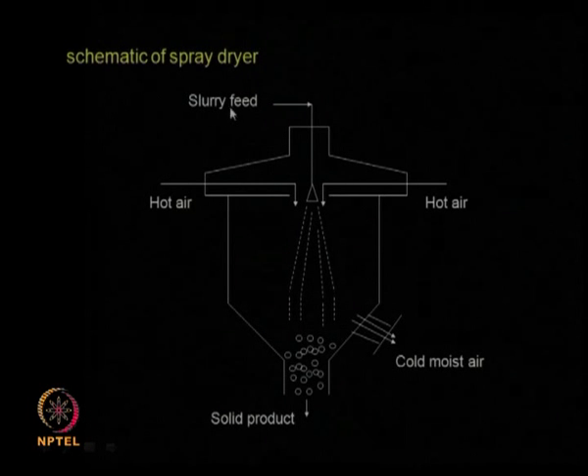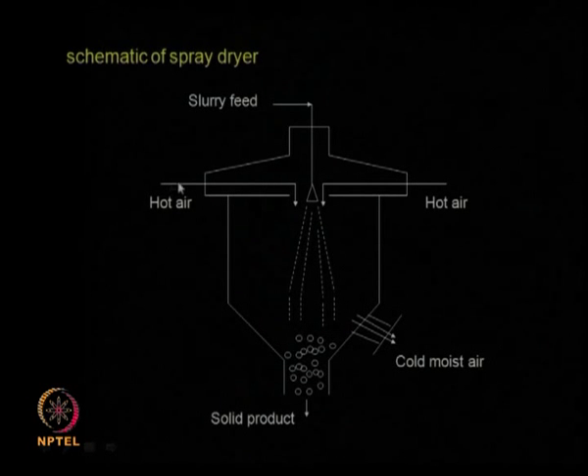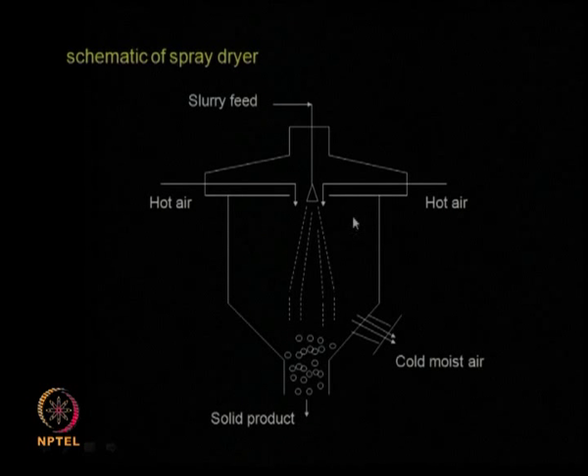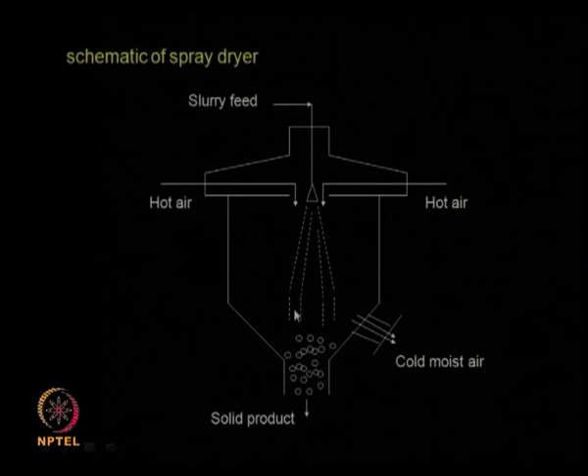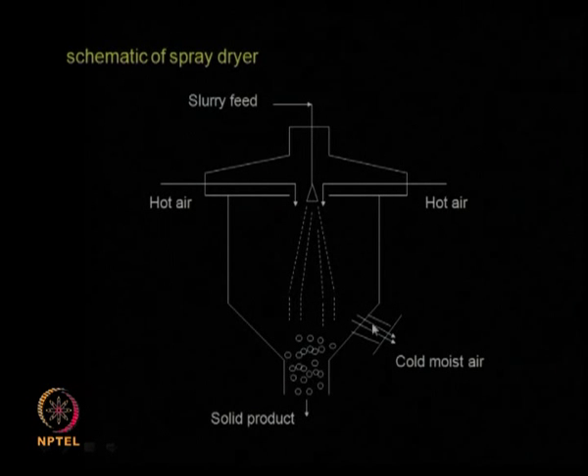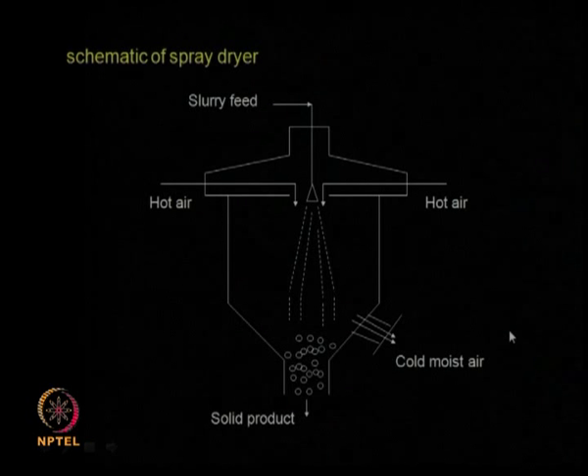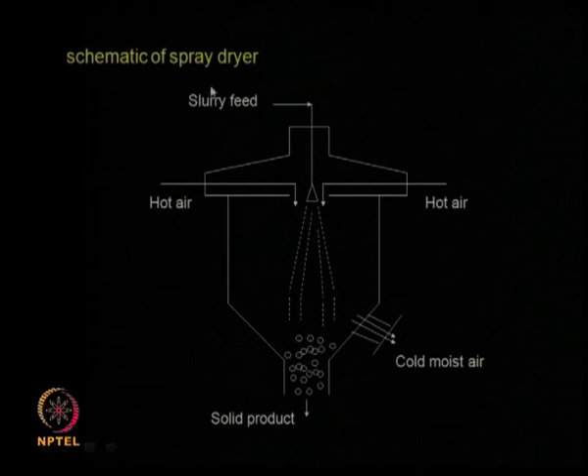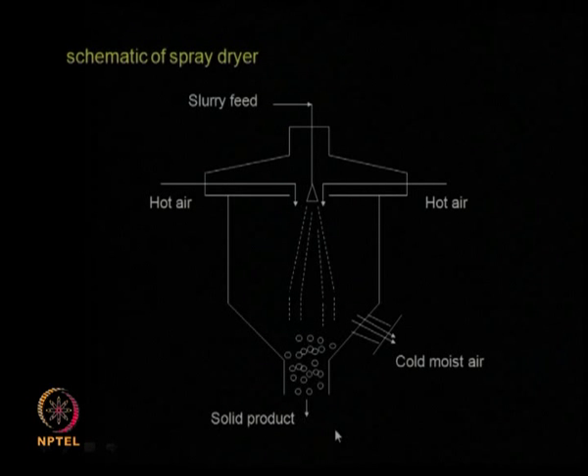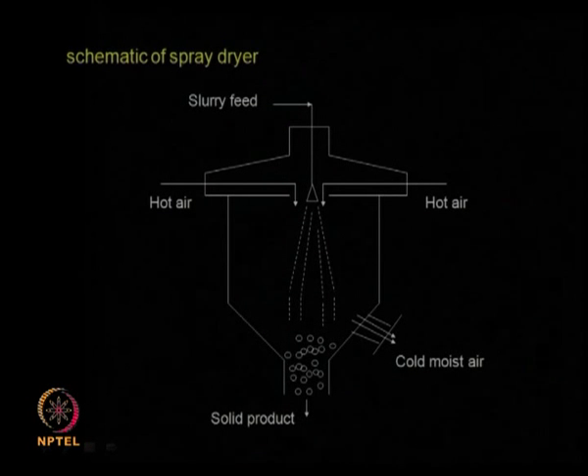In a typical spray dryer setup, slurry is fed from the top, comes out through a nozzle as a fine spray, and hot air comes in contact so the solvent or water gets evaporated. Fine micron-sized particles are formed and collected. The hot air becomes cooler and moisture-laden as it gives up heat. This can be done continuously — continuously feeding slurry, sending hot air, and removing solid product. This is a very good technique widely used in the food and flavoring industry.